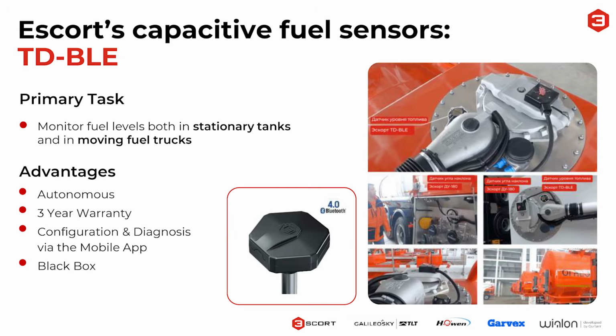The length of the sensor is adjustable, making it suitable for any tank of any height. We do not generally recommend installing the sensors in tanks shorter than 15 centimeters, because the fuel fluctuations inside are too strong to offset with any filtration algorithm. It's possible to install the sensor in a tank shorter than 15 centimeters if it's a diesel generator tank, for example, but in other cases we generally do not recommend it.